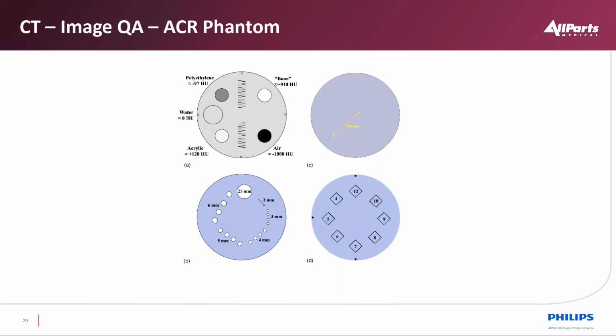Also, to verify our measurements, when we're measuring items within the patient, we have to validate that our scaling, our reconstruction, actually matches what's in the patient. So you'll see 2 pins in the phantom in the upper right. That represents a distance that we should be able to measure on our CT scanner and get 100 millimeters between those two. That tells us when our reconstruction is good.